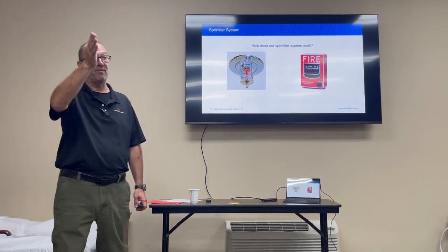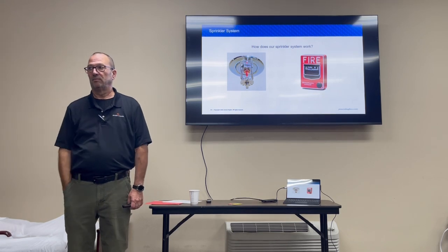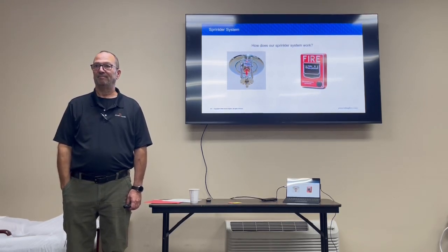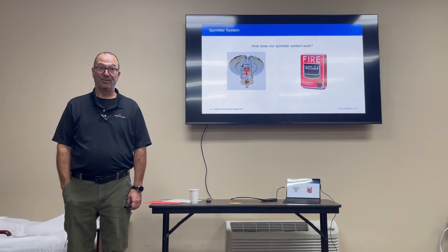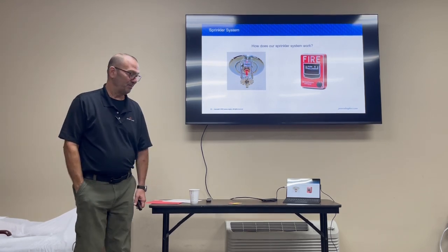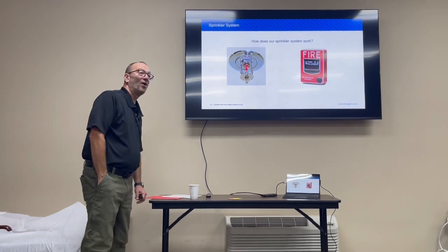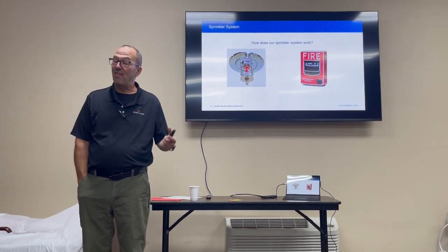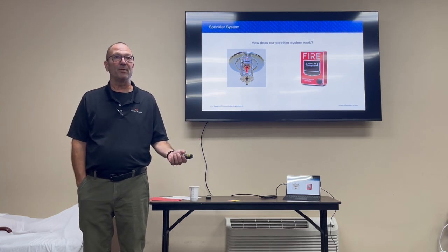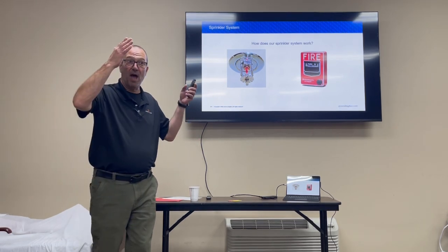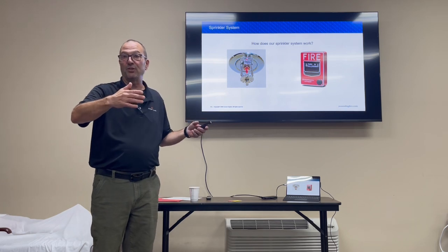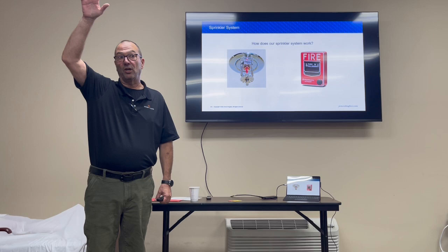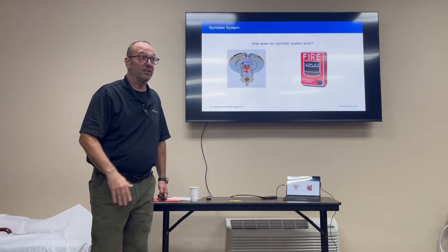So now they say, okay, fire's out, go shut down the sprinklers. Where are the sprinkler shutoffs? That's important for people to know. I asked Jim this morning, and it was the service hall is where that is. At least for that one, we'll verify the other. But yeah, that's a pretty big deal, because now everybody's running around trying to figure this out. Do the math. It takes 10 more minutes, 15 more minutes to do that. Then when they shut it down, it slows down the sprinkler, but it doesn't stop. So then you gotta drain the system to get it to stop.